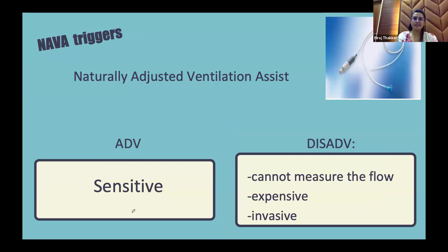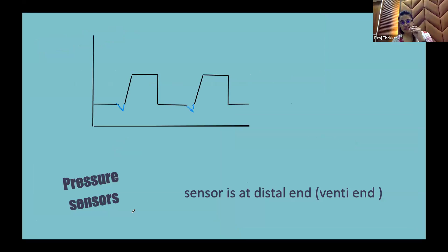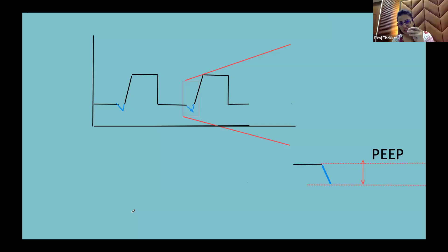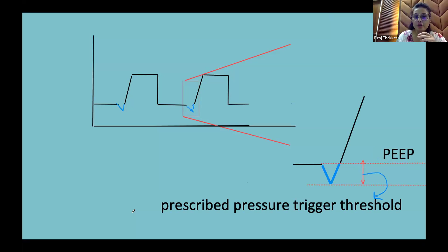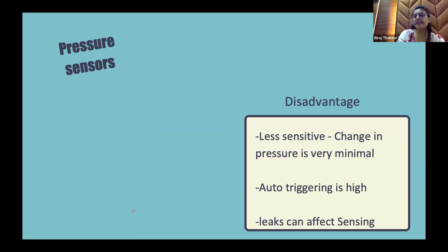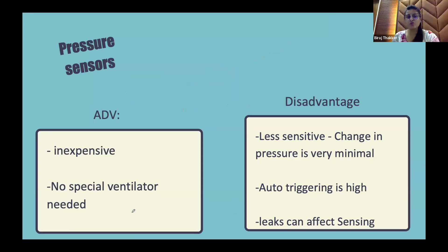The fourth one is the pressure sensors. These detect the change in the pressure, and depending upon the change, they detect the breaths and trigger them. As soon as a patient initiates a breath, there will be a drop in the pressure. As soon as the prescribed pressure trigger threshold is achieved, the breath is detected by the ventilator, and the mechanical breath is given. That is how the pressure sensor works. But the disadvantage is that it is less sensitive. Change in the pressure is very minimal in the newborn. Auto triggering is also very high with this, and leak can also affect the sensing. It is inexpensive and sometimes no special ventilators are needed.